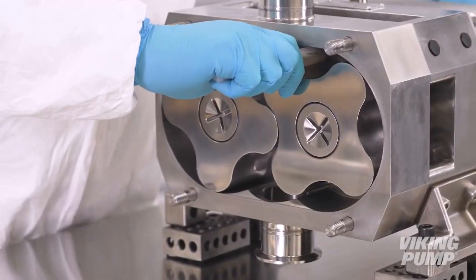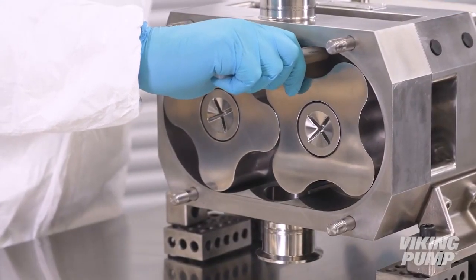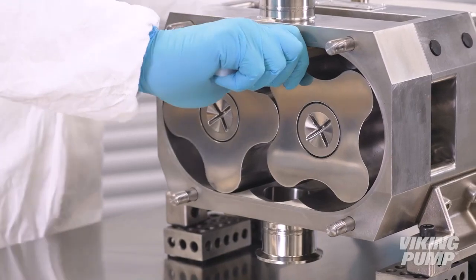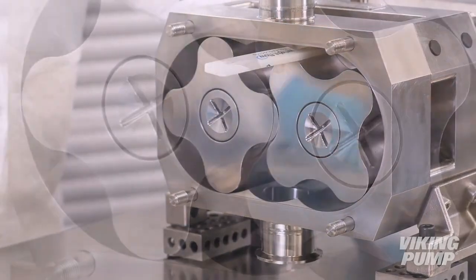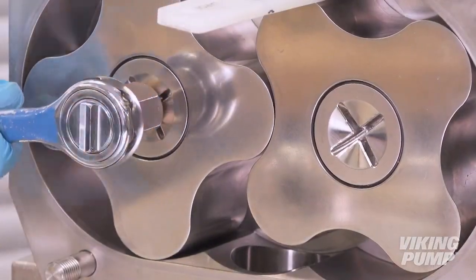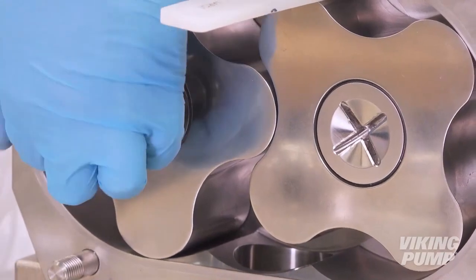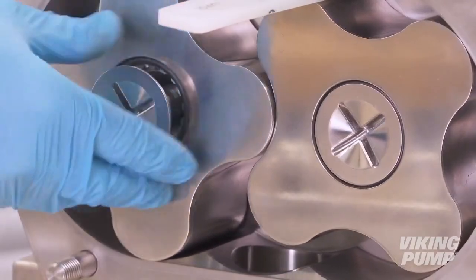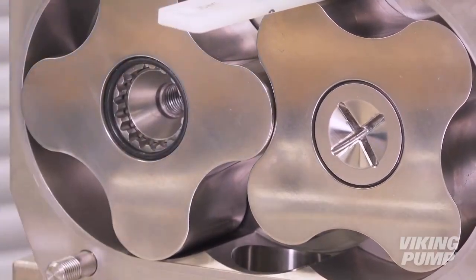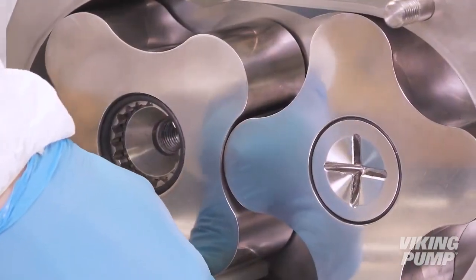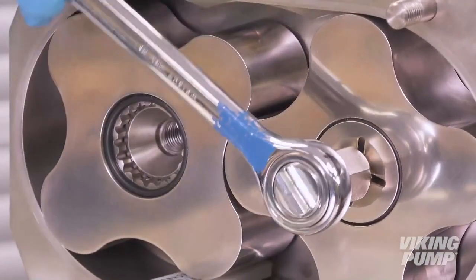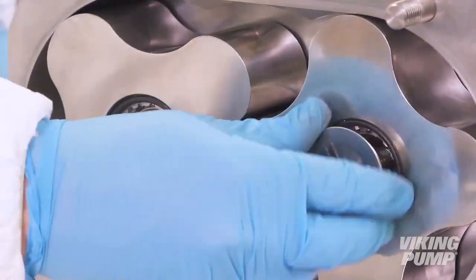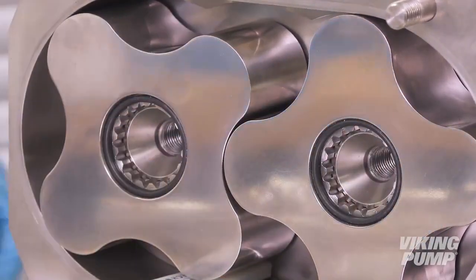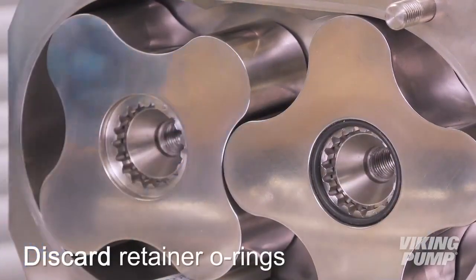Next, to prevent the rotors from turning, insert the rotor locking tool provided with the pump or a dowel made of plastic or other non-metallic material between the pump body and rotor. Using the provided cross socket and a ratchet, loosen and remove the rotor retainers. Remove and discard the retainer O-rings.